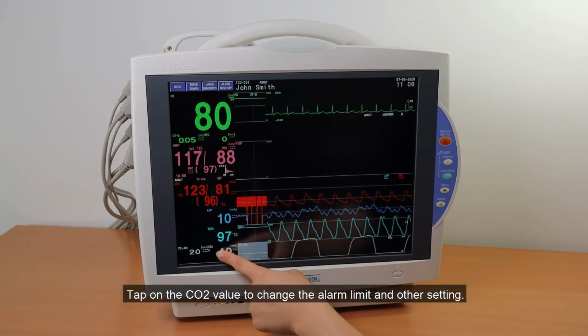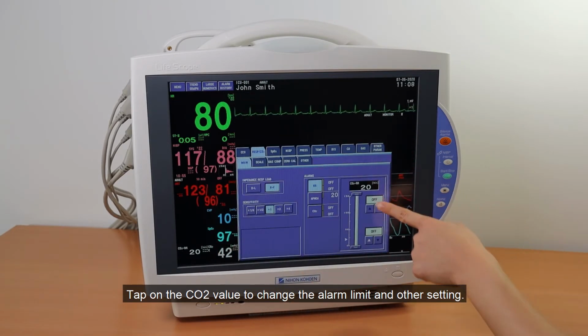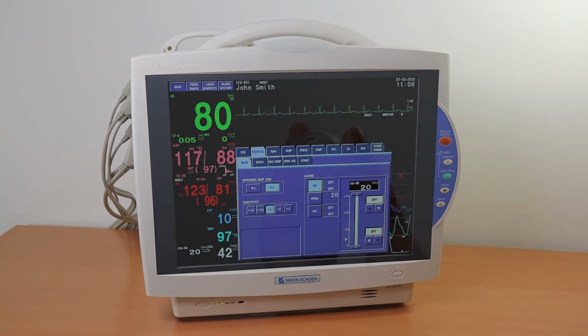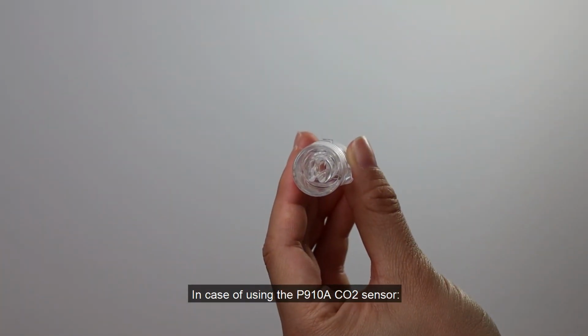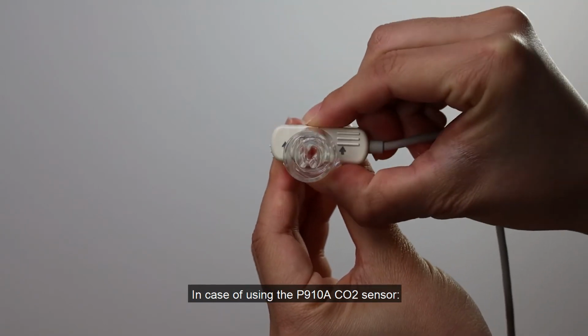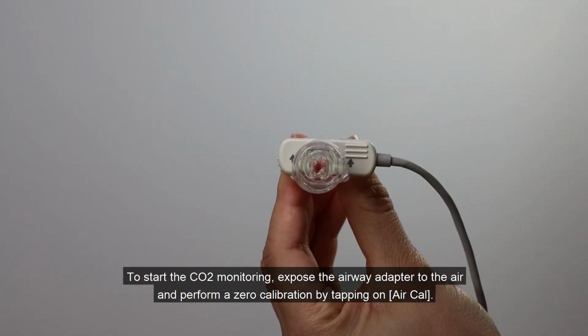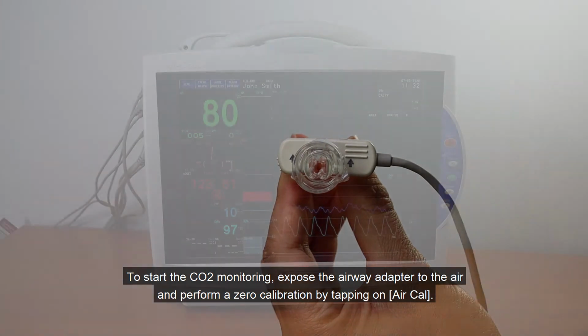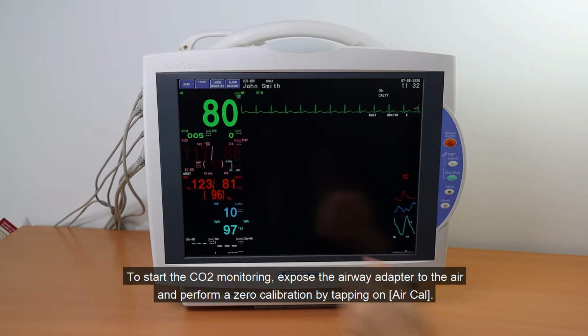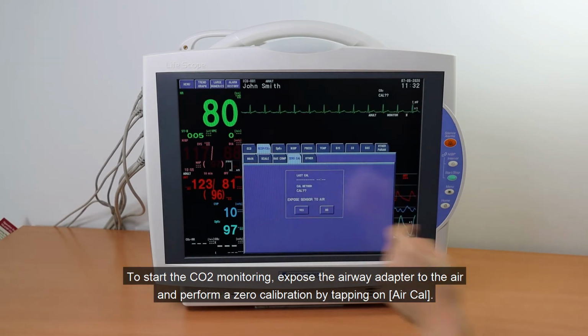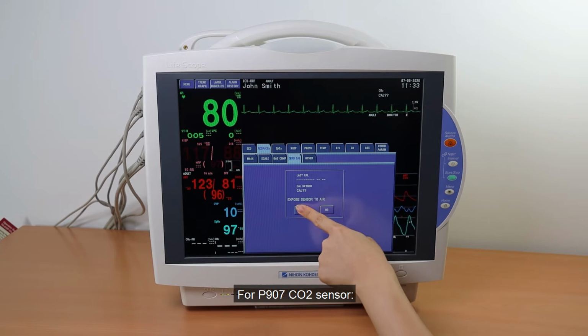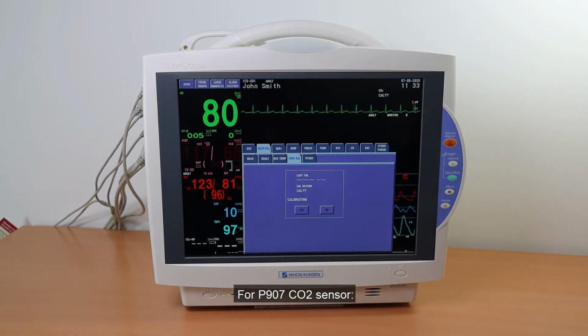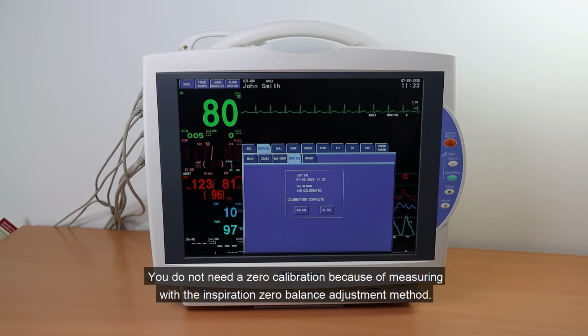Tap on the CO2 value to change the alarm limit and the other setting. In case of using the P910A CO2 sensor, to start the CO2 monitoring, expose the airway adapter to the air and perform a zero calibration by tapping on Air Cal. For P907 CO2 sensor, you do not need a zero calibration because of measuring with the Inspiration Zero Balance Adjustment method.